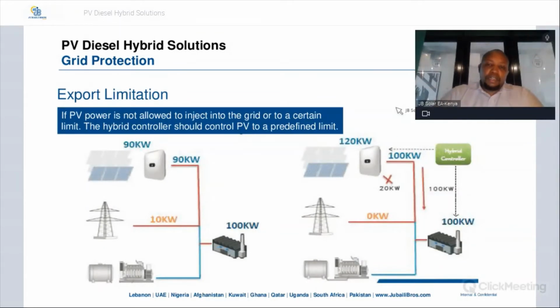Then another feature, now this is in grid protection, where we have export limitation. In several countries, we are not allowed to export power from, let's say, the diesel generator or from the PV back into the grid. And in this case, if exporting is not allowed, or there are set limits as to how much power can be sent back to the grid, the hybrid controller can set these limits, or even cut off feeding into the grid.